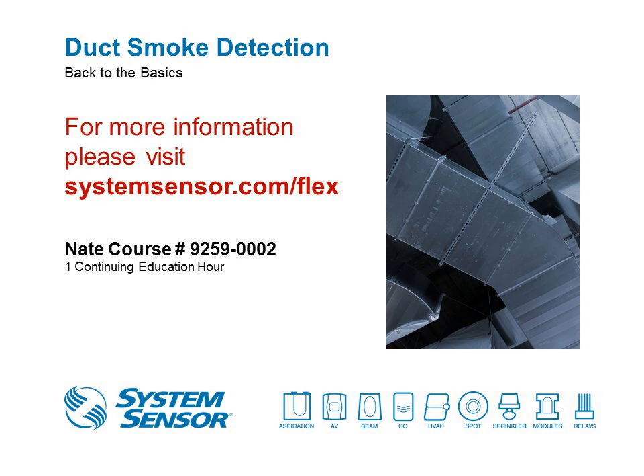You can't always fit all the needs for the ductwork on our standard tube length. Some of the tubes you have to cut down. Other ones you have to protrude to the other side. What we do recommend is that you get a representative sample across the width of the duct by having at least 10 to 12 evenly spaced sampling tubes or sampling holes across that ductwork. I know it's kind of a vague thing, but there's not a specific hard and fast answer. Okay. Yep. All right.